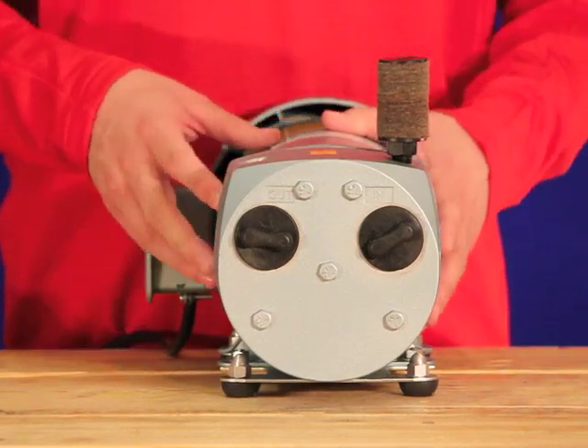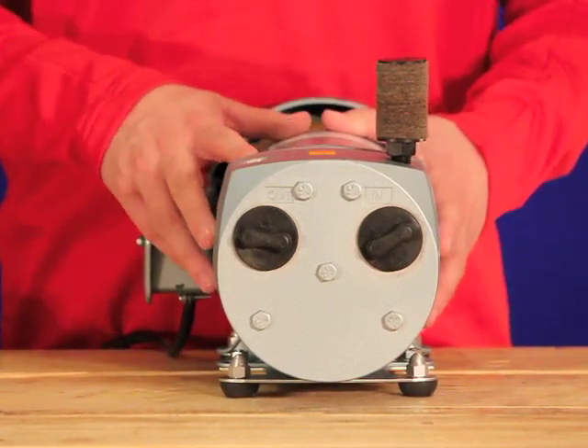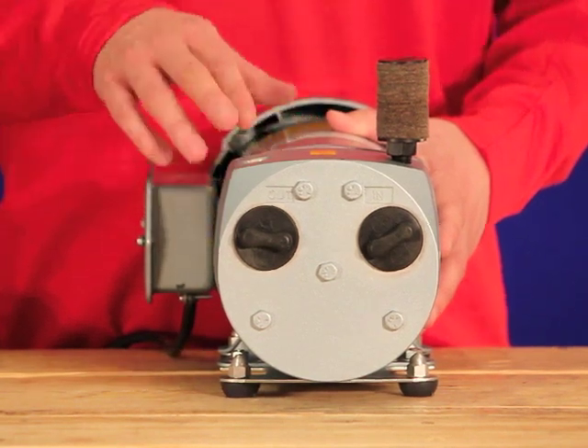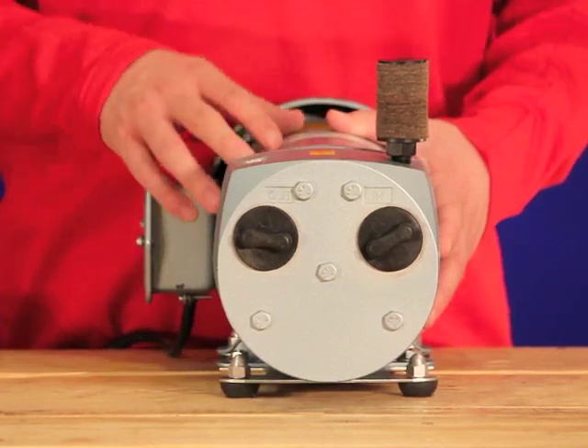We recommend you come from the pump with brass or galvanized. These pumps do run hot. You can switch to PVC after you use fittings to come out.